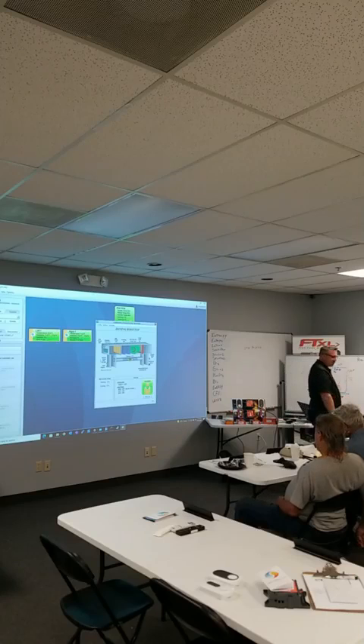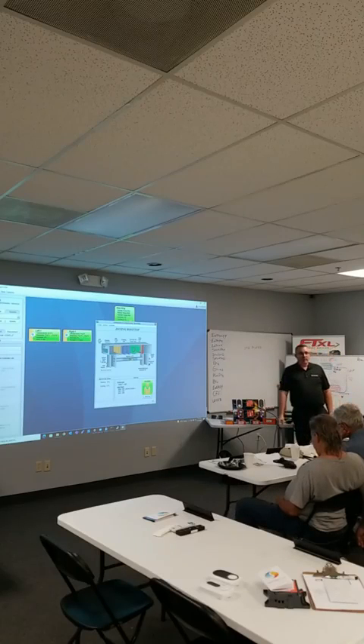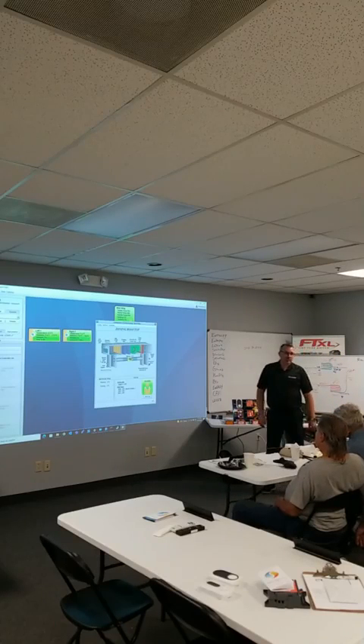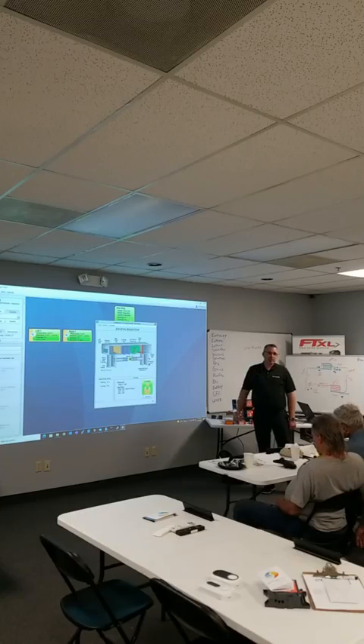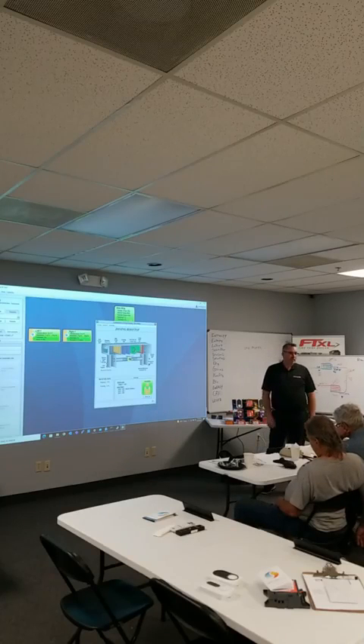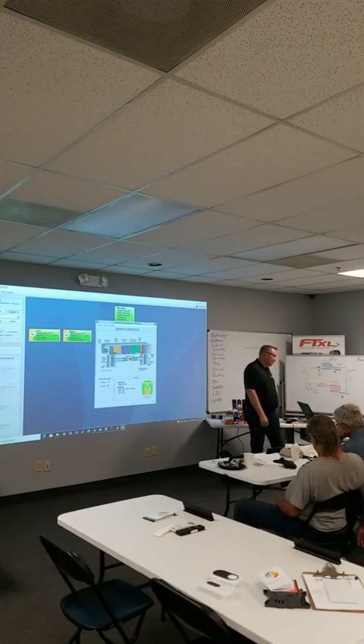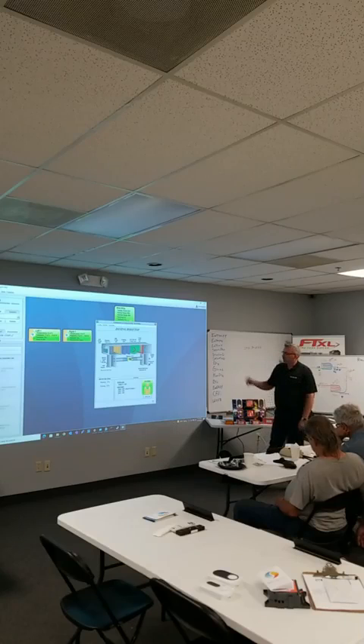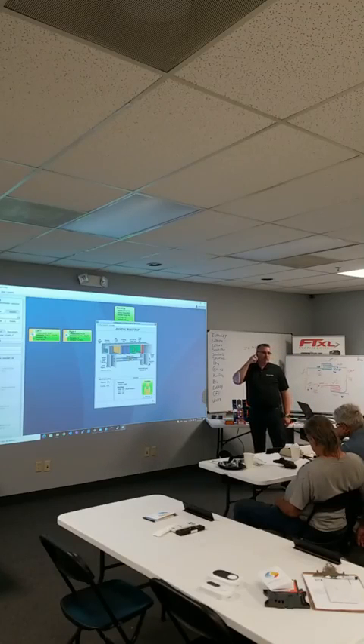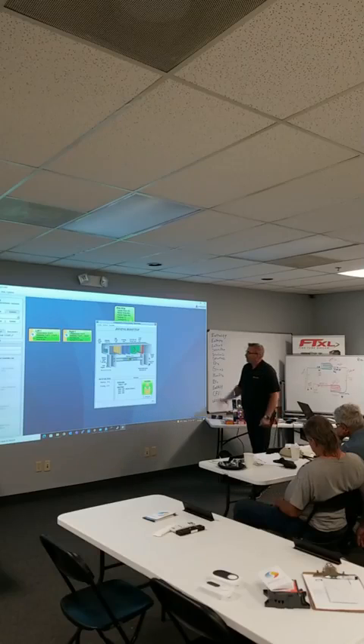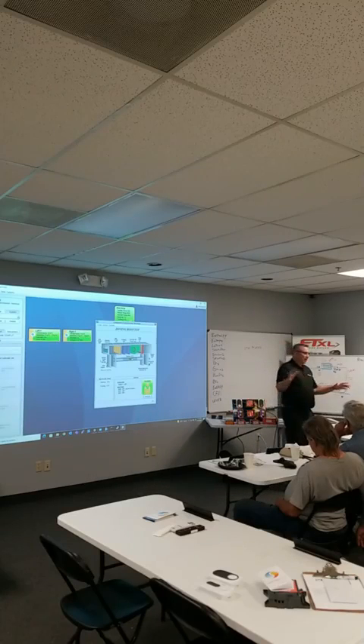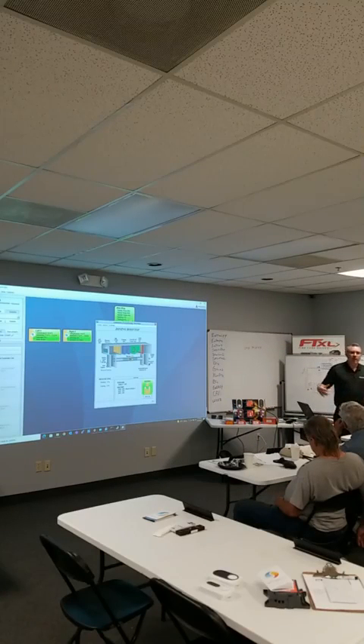So I said, look, man, the PROLON system's fine. What's not fine are all your zone dampers. You're gonna need to get up there. You need to set them. You need to set the stops. You need to cycle power. You need to get your bypass damper hooked up the right way, and then go back and test it. So even though it's not a big complicated system, there's a lot of stuff that you can do.